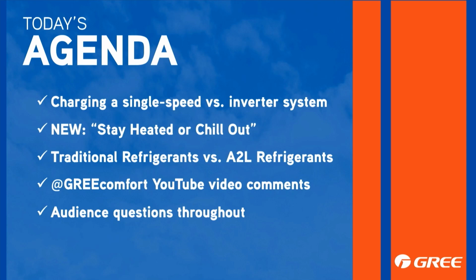Right. So if it fails, your compressor's failed. If one of those little things fails, it's done. Whether that's a 2-speed compressor or some kind of weird inverter hybrid type of compressor that I've recently seen, they're adding more components, moving components, operating components within a hermetically sealed chamber. I'd rather replace the board than have to swap out a whole compressor every single time. That also makes compressors a lot more expensive, right? Especially if you want to take it one step further and compare it to a 2-stage compressor. The top of that scroll plate has got to turn. I can't think of the name of it off the top of my head, but it's another mechanical part that could fail in a scroll compressor.